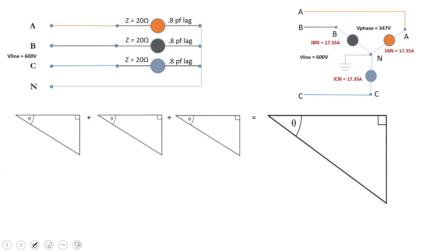Remember in Y, the rule is that V-line equals V-phase times root 3, so V-phase equals V-line divided by root 3. In this case, 600-volt line voltage gives us 347-volt phase voltage. We can then calculate the current in each phase by dividing the phase voltage by the impedance in each phase, which comes to 17.35 amps.